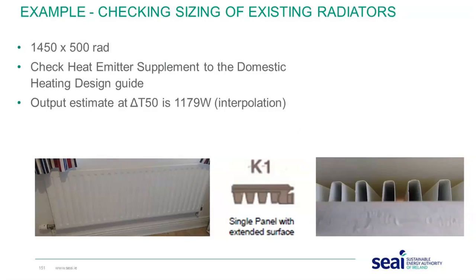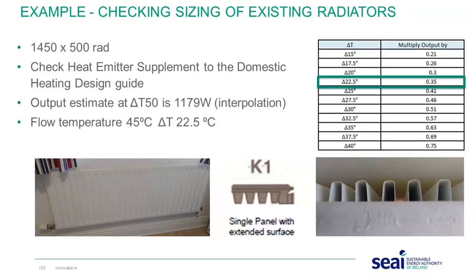Now we know for the case of a heat pump, we're not going to operate it at a delta T of 50. So in the case of this example, we're going to have a flow temperature of 45 degrees. Our delta T is going to be 22.5 degrees. So what we need to do is look up the conversion factor in the domestic heating design guide. And it tells me here on the image on the right, at 22.5 degrees, the factor I need to multiply the output by is 0.35. So when I multiply that factor, 0.35, by 1179, I get an output of 412 watts. So that's an example of how we would assess the output of an existing radiator.